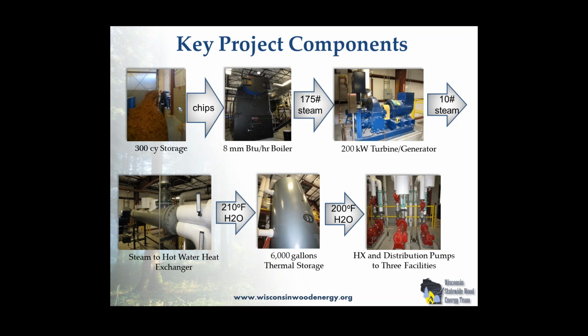So it takes chips, 300 cubic yards of storage, sends them into the steam boiler, comes out at 175 psi, goes through a 200 kW turbine generator, then a steam to hot water heat exchanger on the flip side, just a little shell and tube heat exchanger. They store 200-degree Fahrenheit water in a 6,000-gallon thermal storage tank.